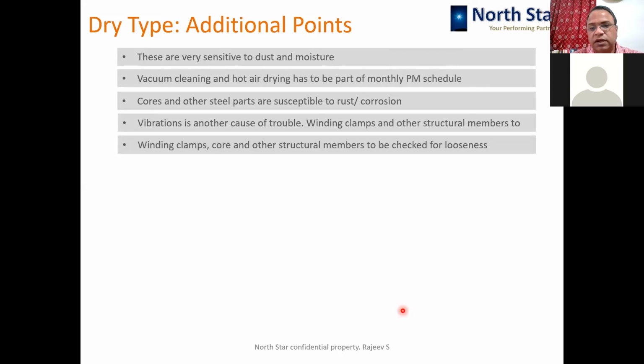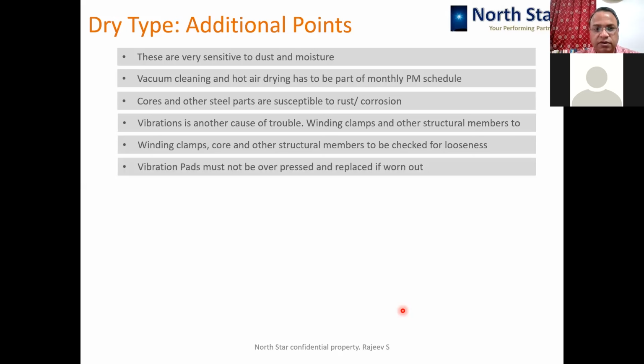Okay, so from time to time tightness is to be ensured. All the hardware of the dry type transformers is to be tightened whenever you're doing the PM schedule, and check for the looseness. Torque wrenches are to be used for all metal to metal contacts.